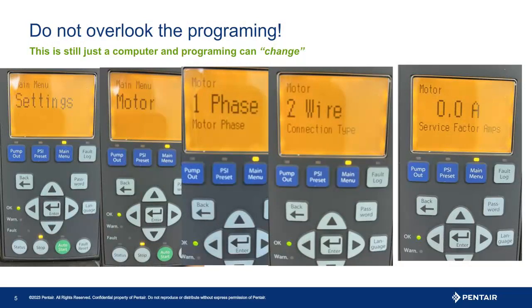First thing I would check is the programming. Now on the screen you see the motor menu. A point to remember is that if you upon initial startup were to hit just enter, you would program single phase, 2-wire, and most importantly 0 amps. And of course, if you do this and start the drive, any motor that is in working condition will of course pull more than 0 amps at start. I also recommend checking the amp setting first step, as you never know what might have happened to the system or if the owner might have changed something unknowingly.